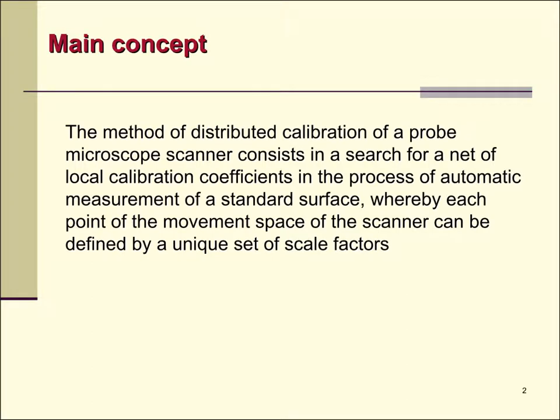Main Concept: The method of distributed calibration of a probe microscope scanner consists in a search for a net of local calibration coefficients in the process of automatic measurement of a standard surface, whereby each point of the movement space of the scanner can be defined by a unique set of scale factors.